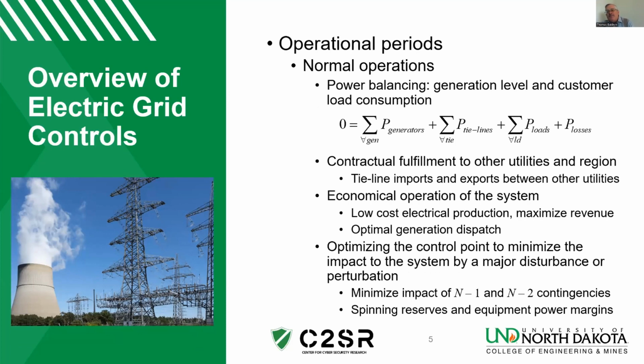So the balance of power is important at various levels in the system. And so we have our basic equation here that defines the balance of power. All generation power in a system must equal the power being exported in or out via the tie lines to other utilities. And the generation and tie lines take care of the load power and any losses that take place in the system due to the resistive loss of conductors and corona.